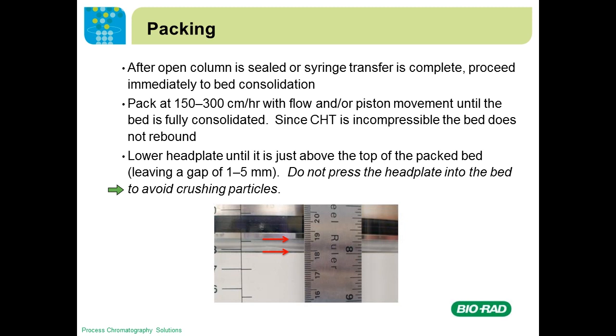People ask: what if I bring the top flow adapter down until it's just kissing the top of the bed? The answer is that's fine. If you break one or two particles, that's okay. If you break a million particles, that's going to be a problem. We recommend leaving a gap of 1 to 5 millimeters. This is also why it's important to have the column level — if you see a 5 mm gap on one side but the column isn't level, on the other side you may have already pressed the adapter into the particles. This isn't an issue with compressible resins, but it is with CHT and other incompressible resins like silica, controlled pore glass, or zirconium.